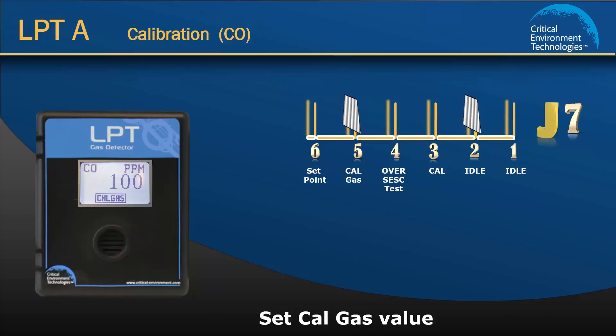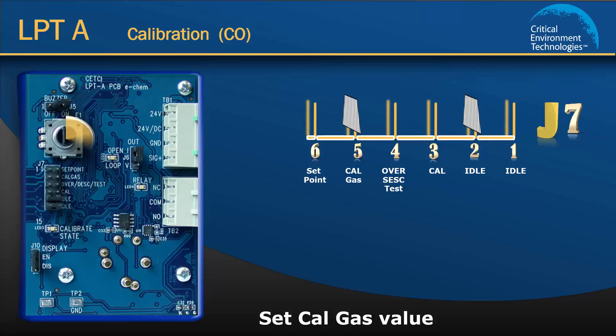By default the cal gas value is set to 100 ppm and calibrated by the factory using span gas at 100 ppm concentration. Therefore in this example the display should show 100 ppm. If it is not showing 100 ppm or if you are using a different cal gas concentration, use the rotary encoder dial to adjust the number. The ppm number on the display should match the cal gas concentration ppm.